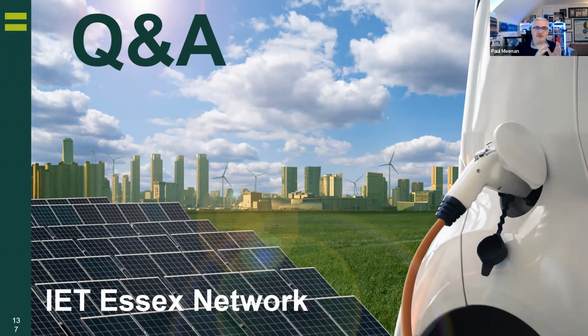The reason 32 amp was chosen is because the most common fuse in most homes of a certain age is 32, your ring main. So it was decided that if you have a ring main, then fine. But if you want to put a 40 amp AFDD on a shower, do it—most showers should fit within 32 amps anyway, to be honest. There's nothing stopping you. Remember, the regs is a minimum standard, it's for you to apply your engineering judgment. So if you want a 40 amp one, go and find a 40 amp one. Remember, in the hierarchy of legislation, the wiring regulations is still a guidance note—just one you need to know really well, so you can have a defence in a court of law.